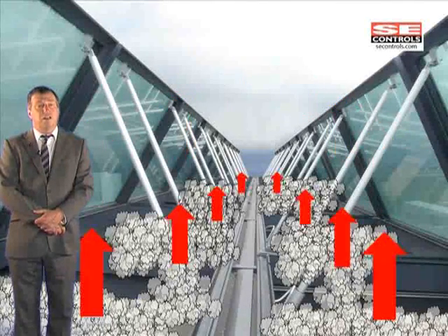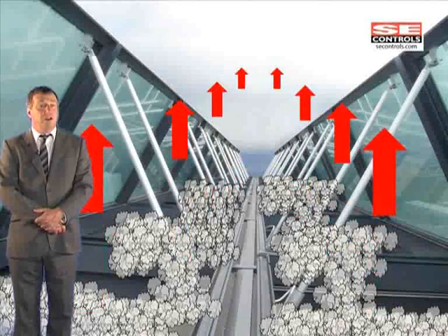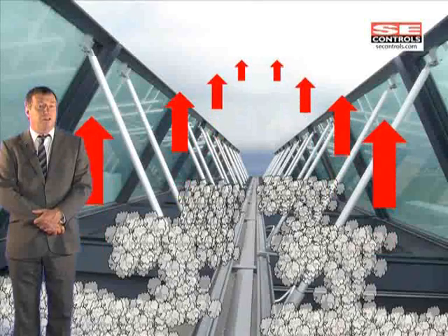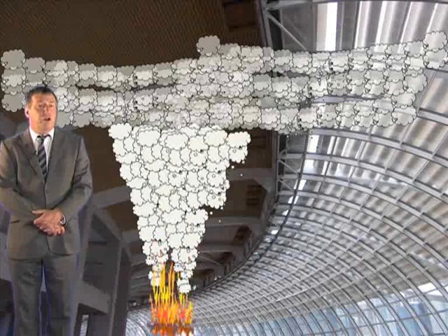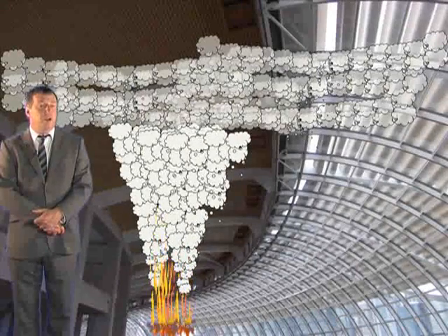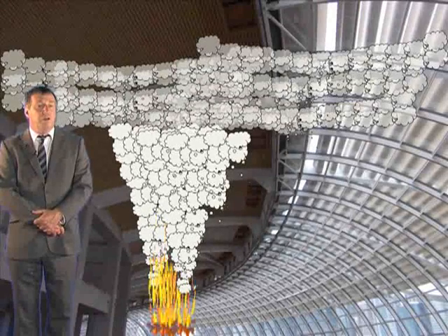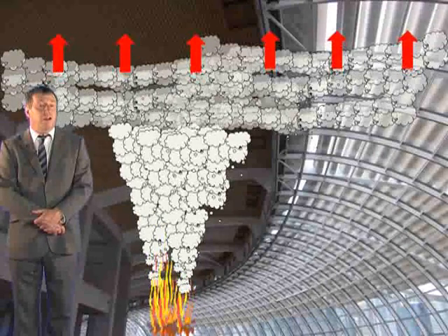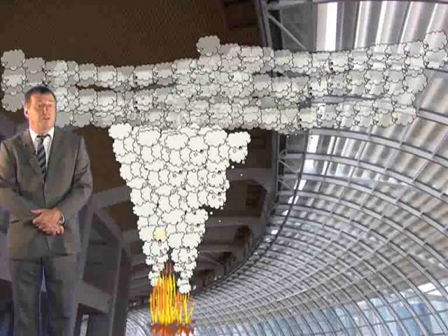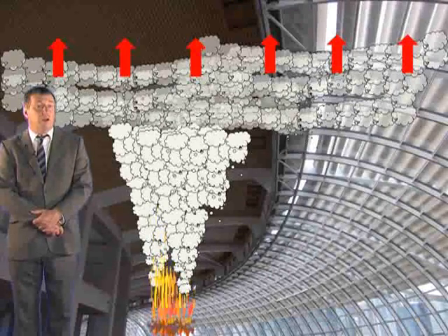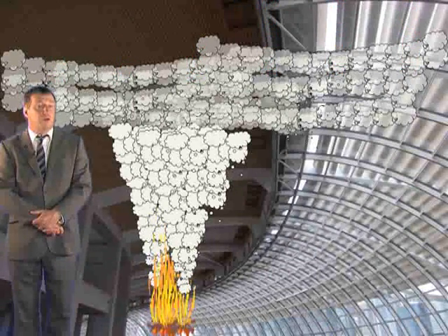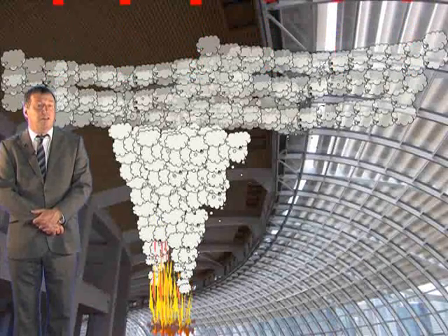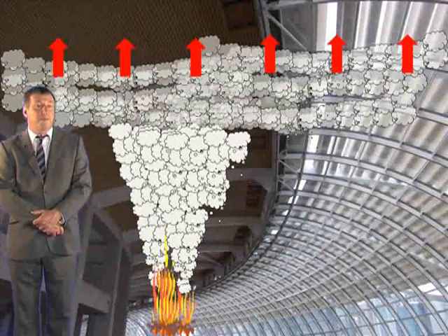The advantage of a natural ventilation system over mechanical is that it is very simple and reliable, and it can cope with a wide range of fire conditions. In the event of a fire exceeding the designed fire size, for whatever reason, the exhaust rate will increase due to the smoke layer being deeper and the smoke being at a higher temperature. Furthermore, the base of the smoke layer will descend, so less smoke will enter the smoke layer due to less entrainment of cool air. In other words, the system is to some extent a self-compensating mechanism.